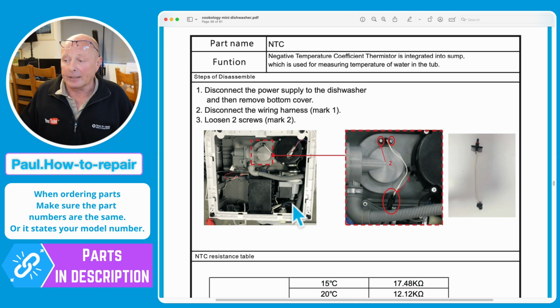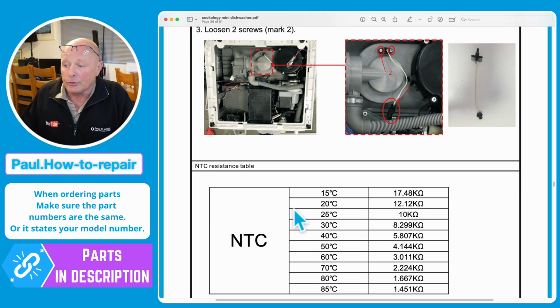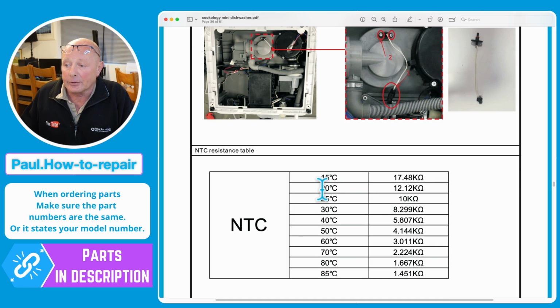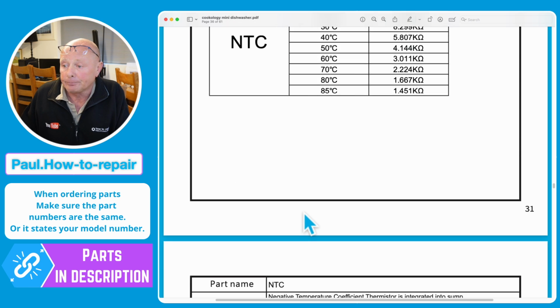NTC sensor - again I've got a detailed video on NTC sensors on how they work and how to go about testing them. But as you can see here in the exploded chart, if you have a room temperature of 20 degrees you should be getting about 12,120 ohms resistance if it's at the correct working parameters.